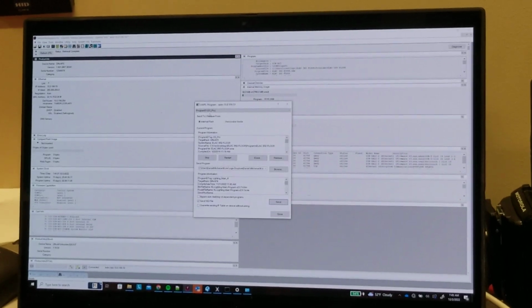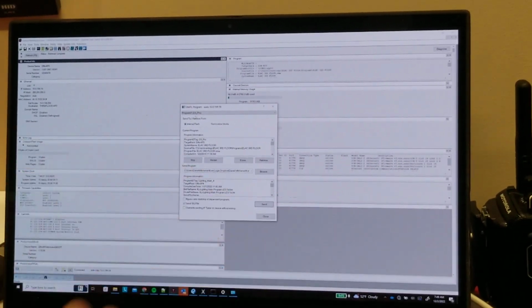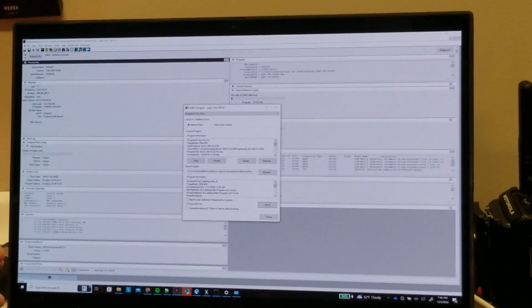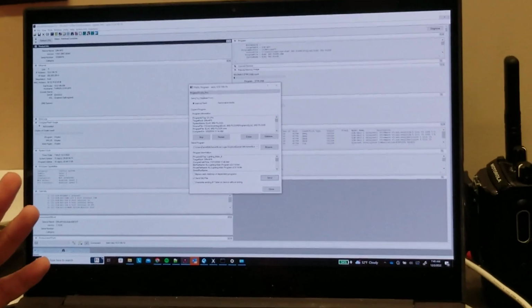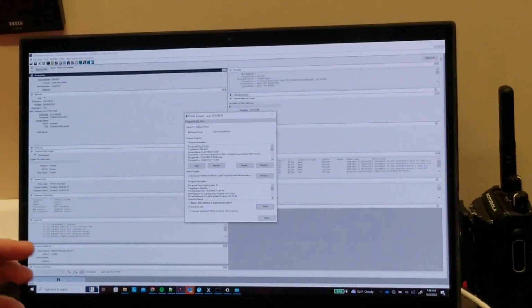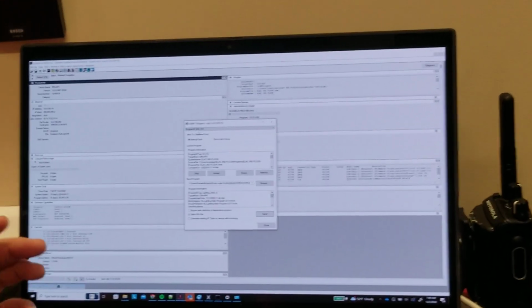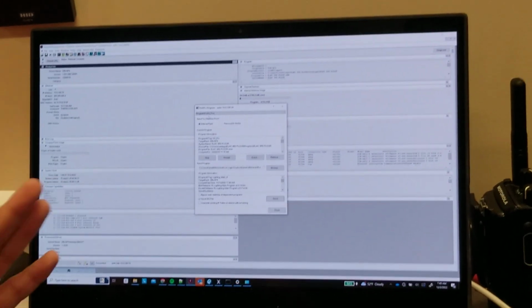You have 5 processors in the building, and you'll have a program per processor, not 10 on one processor. And just so you understand too, the reason we have it divided up that way is because even though it can run up to 10 programs, it has a limited amount of space on it. So instead of running 10 small programs, we're running one big program per processor.